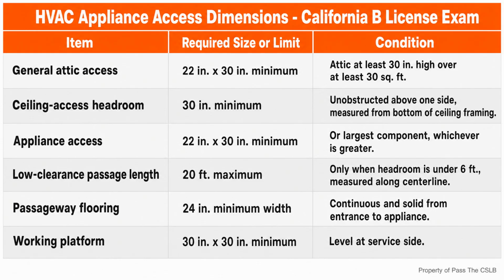Imagine a replacement air handler with one cabinet section that cannot clear the framed opening. The wrong response is to assume the technician can dismantle a factory assembly in any manner necessary. The general B response is to stop and confirm the manufacturer's permitted service procedure, the actual removal dimension, and the framing solution. The source-backed rule here is not that every unit must be disassembled. It is that the opening must accommodate the largest component.